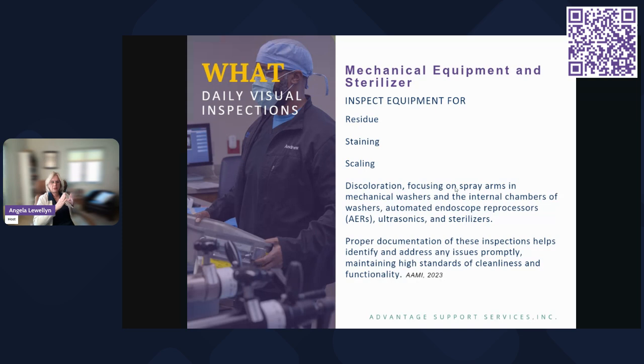Here's a hypothetical: once your technician is going through and doing all the Bowie-Dick tests or the biological testing for steam sterilizers, or even autoclaves if you still have them, they can now document this as well. They're going to visually inspect for discoloration, focusing on the spray arms and internal chambers of the washers, as well as the AERs, ultrasonics, and sterilizers. We have a chart listing all the equipment, and you go through and put your initials to check positive or negative for any of this daily.